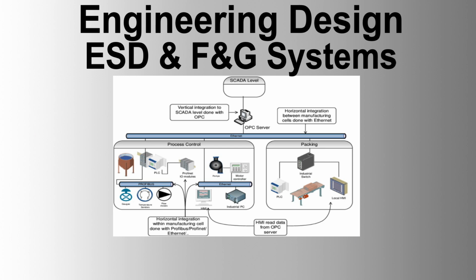Hardware requirements, ESD F&G hardware. General requirements. 1. Card replacement. It shall be possible to replace cards without switching off the power or disturbing the process. Short-circuiting of individual inputs and outputs shall not affect other inputs and outputs.